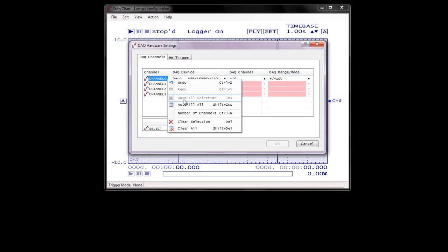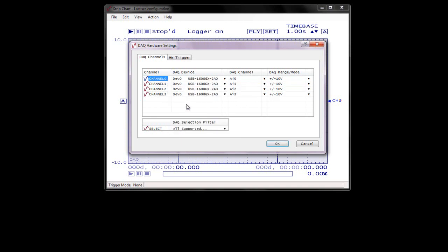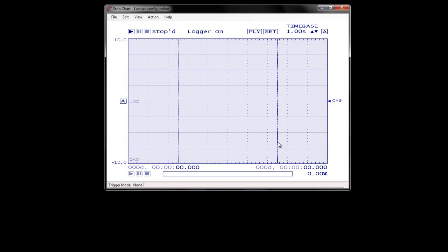Right-click on the first cell in the channel column, Channel 0, and select Auto Fill All from the pop-up menu. The next three channels are automatically added and configured with the same range as Channel 0. Click OK to save the settings.